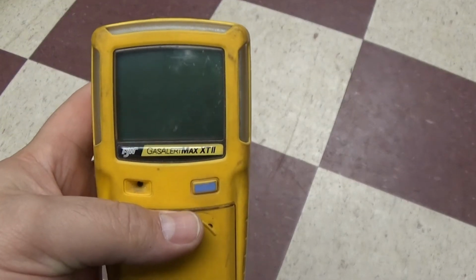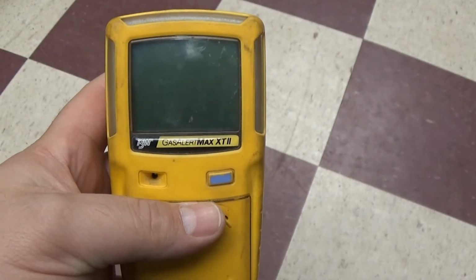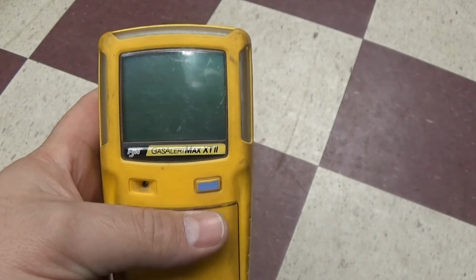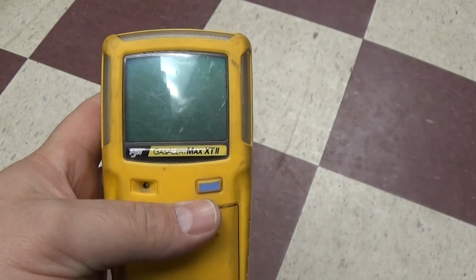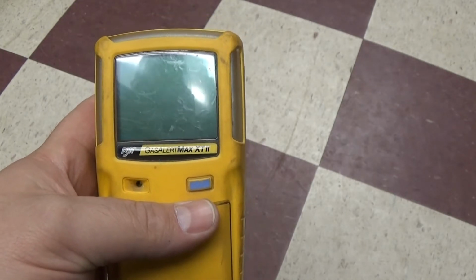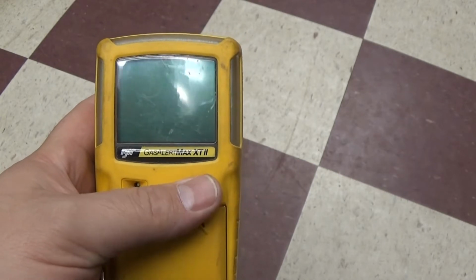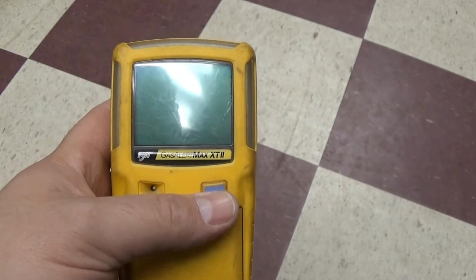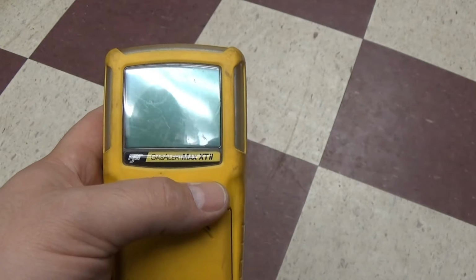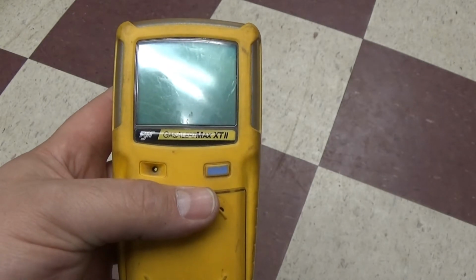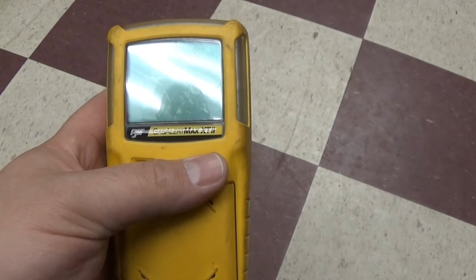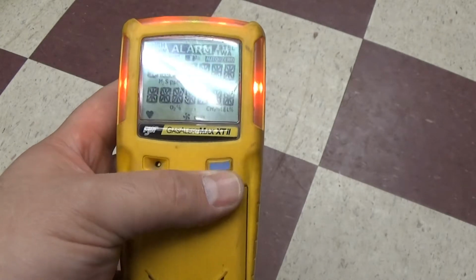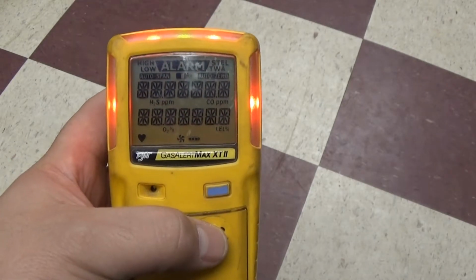At the start of every day, before we do any hot work, of course, we've got to start up the meter and bump test or calibrate depending on what it calls for. It's got to be bump tested every day or every 24 hours or the meter won't let you do anything. So turn the meter on, just push the blue button one time and it goes through its startup process.